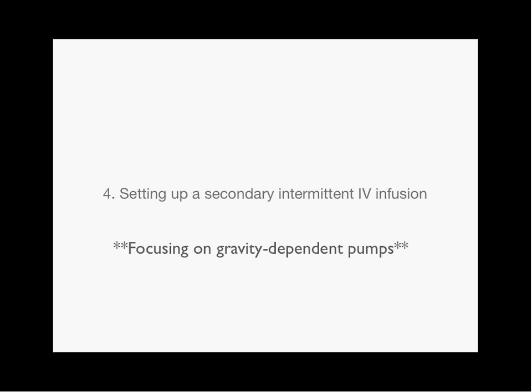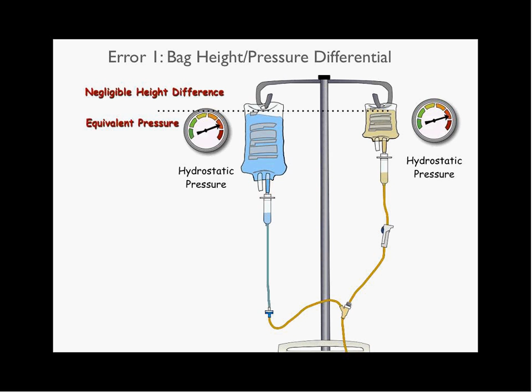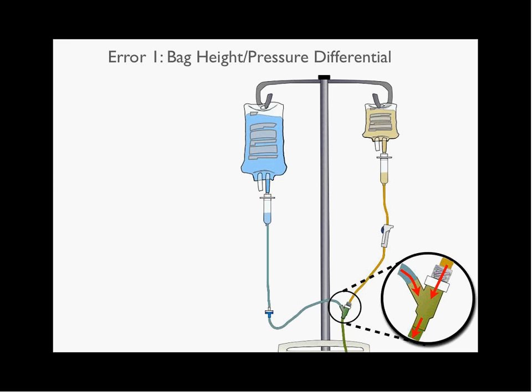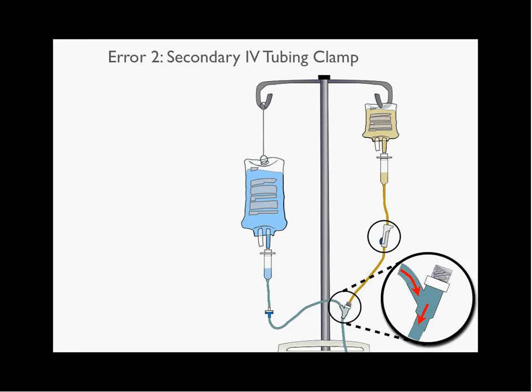From the literature, and one we saw during our observations of nurses, is the failure to create sufficient differential between the primary and secondary IV bags. In this wrong setup, the primary and secondary IV bags have a negligible height difference, resulting in nearly equivalent hydrostatic pressures. So the resulting setup is that both secondary and primary fluids will run together and be administered to the patient at an indeterminate rate. Another issue from the literature and from our observations is the clamp. The secondary fluid cannot flow when the secondary infusion is started on the pump, and the primary fluid will flow at the rate intended for the secondary fluid.